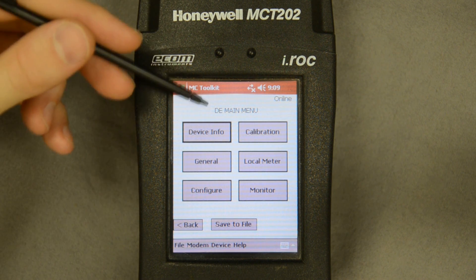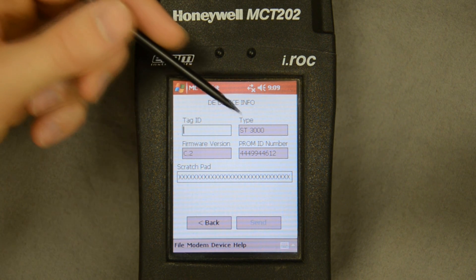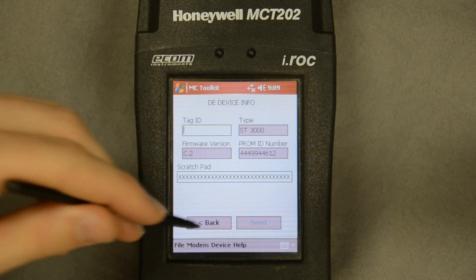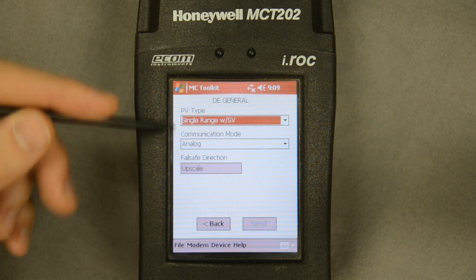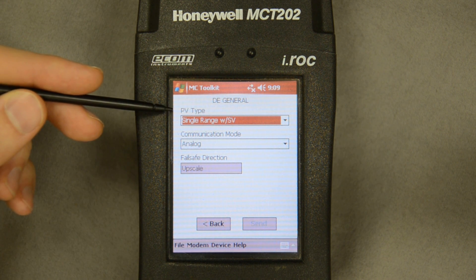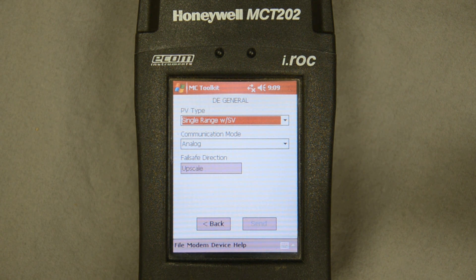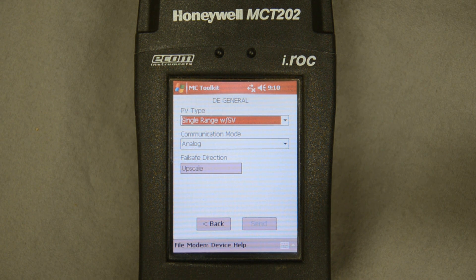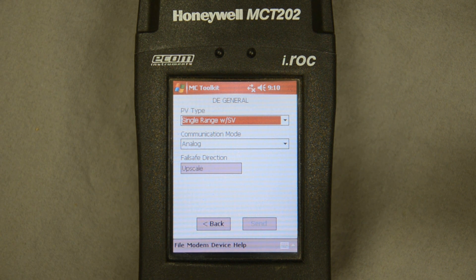I'll start uploading all the device data. Here's the main menu. Going into the device menu gives me pretty much the same information as the front page — the tag ID and specifics of the PROM on the electronics. In here I'm getting information on the process variable; right now it's set up for single range with the secondary variable being temperature. With DE devices I can communicate either analog 4 to 20 or with the actual digital square wave, which was the first communication protocol for smart transmitters back in the early 1980s.